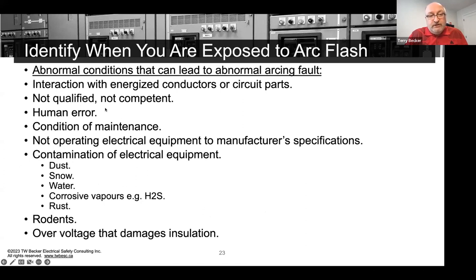I've talked about interaction. Obviously, if the worker is not qualified or competent, they make a mistake, or due to human error, fatigue being one of the top items probably on that list, that leads them to make an error. Condition of maintenance is something that does need to be assessed, and I recommend that the worker does it in real time using look, listen, and smell, and I've got a video coming up on that topic too. So we don't operate equipment to its specifications. Obviously, we get contamination, and then rodents, a very common problem, where we overvoltage the equipment. We run it outside of those specifications, and then the insulation gets compromised. So human interaction and other methods where we can get an abnormal arcing fault.